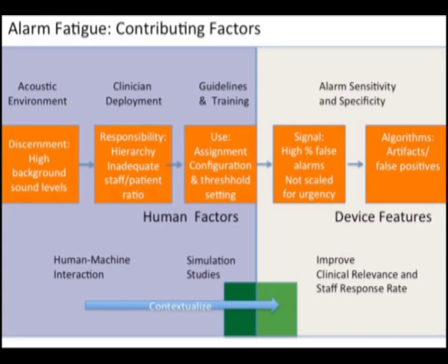So as it turns out, one of the key problems, this is Hopkins again, they were able to reduce the number of false alarms by 25% by simply reducing the thresholds of the alarm. The devices come with pre-programmed alarm alerts, and because we measure multiple types of blood pressure, we can have 6 to 10 different alarms just on blood pressure. Systolic, diastolic, mean, non-invasive, invasive. All these alarms have to be addressed.